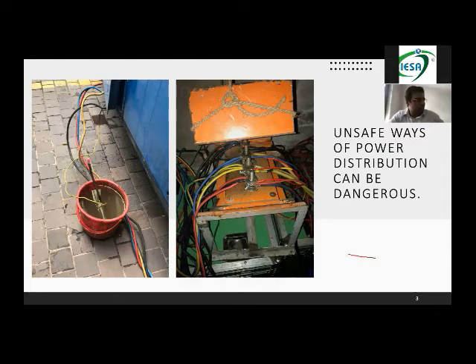This wire, as per the rules, has to be of the same size as the neutral wire. So normally as per Indian electricity, the cables we are getting, we are always having 3.5 core aluminum armored, you must have heard. So what does that mean? That the 3 cores have to be of the same size and that 0.5 is the neutral. So the neutral can be half. Whatever is the neutral size, the earthing size has to be the same.